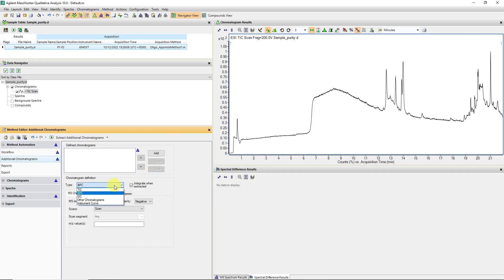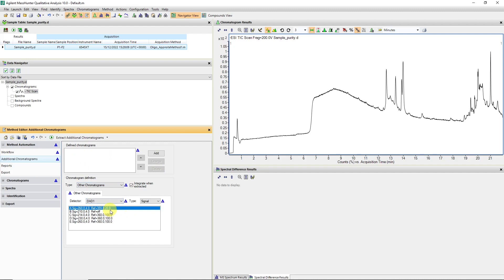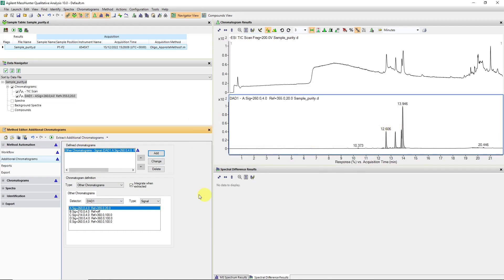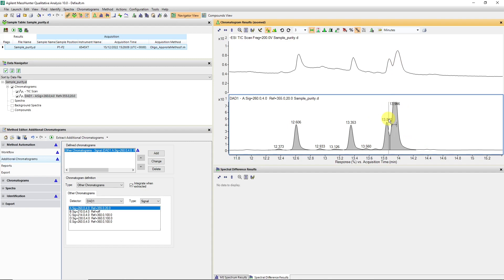I'm going to add other chromatograms. For my DAD diode array detector, I'm going to add the 260 wavelength that it was acquired with, with a reference wavelength at 355. If I now extract, you'll see the peaks get integrated when extracted, and we can see our DAD trace. It sort of correlates with the TIC, but there is a slight delay time because the DAD is normally upstream from the mass spec, and there's some delay in the fluidics path that we'll need to adjust for.